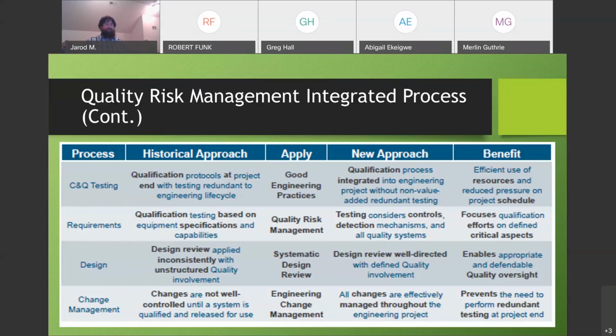So with the application of engineering change management, all those changes within the commissioning and qualification process get effectively documented and managed and integrated, which drives the subsequent testing based on any newly added critical to quality attributes or critical process parameters with that impacted change. So again, it just prevents the need to perform redundant testing at the project end.